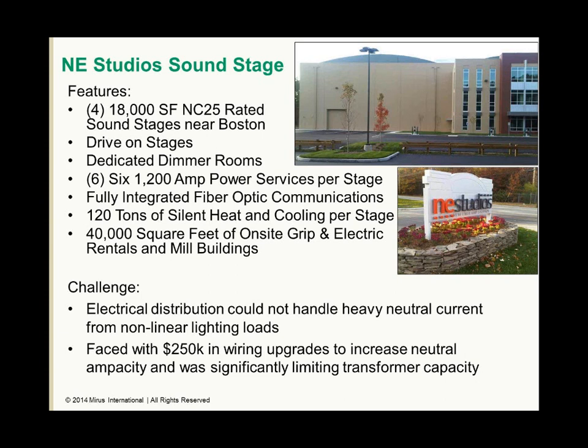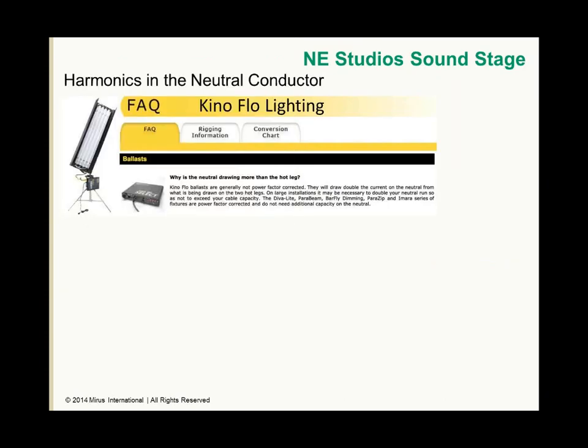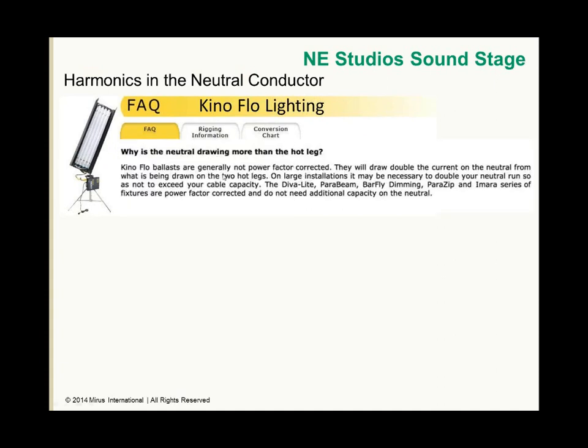One type of lighting used excessively is their Kino Flo. It's very nonlinear, as it states in its literature. You can see here, as I blow this up, it says Kino Flo ballasts are generally not power factor corrected. They will draw double the current on the neutral from what is being drawn on the 2 hot legs.